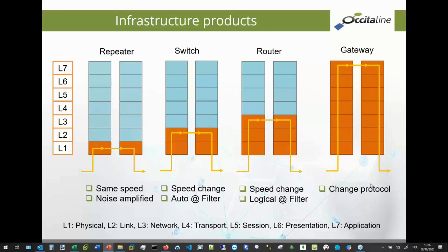The router supports any kind of protocol. It changes the speed because it's just on top of layer 2, and it manages the logical address. The logical address is dedicated to the protocol of this router. If it's a BACnet router, it manages the logical address in BACnet. A router in KNX is a coupler, an IP coupler, and it manages the logical address of KNX. It's the same in LON: it manages the logical address of LON.